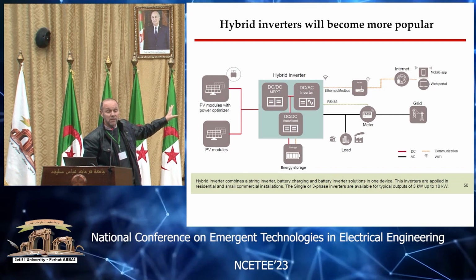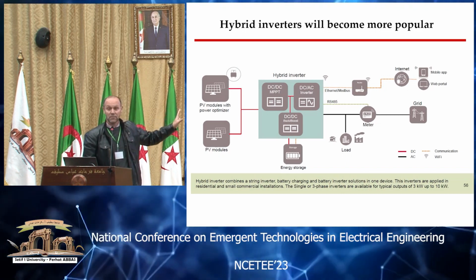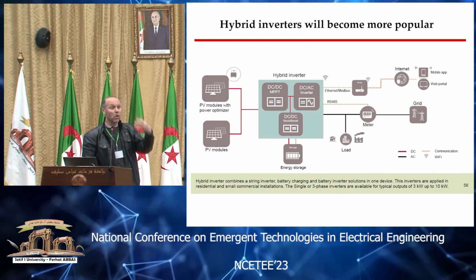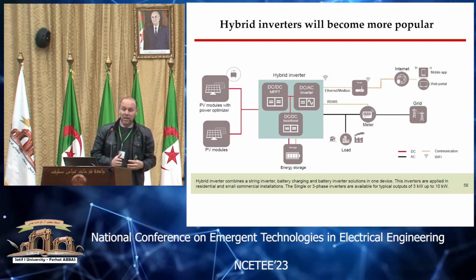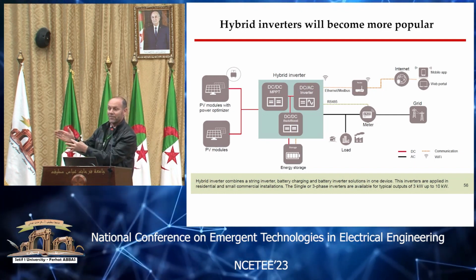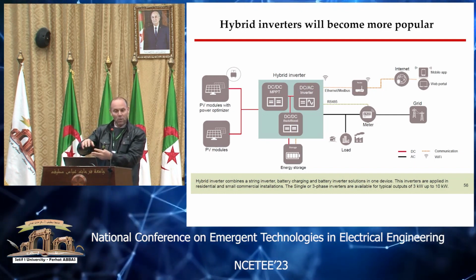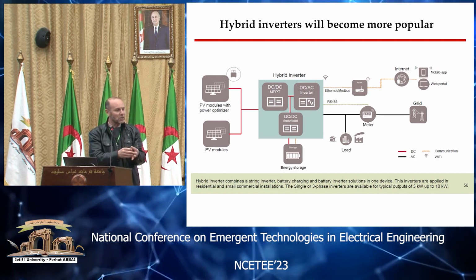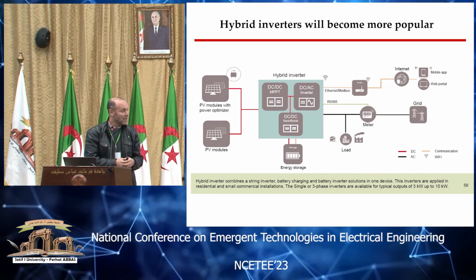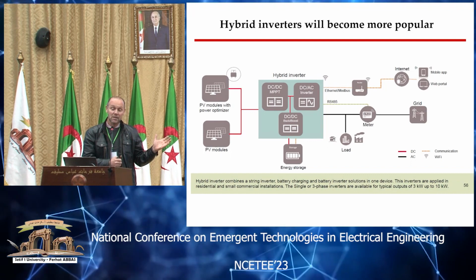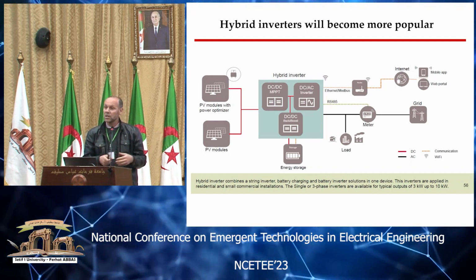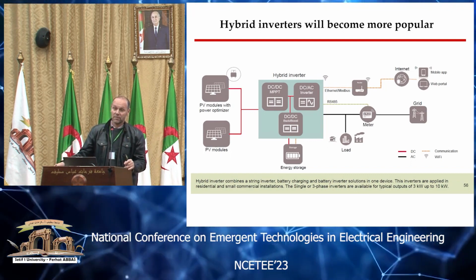Previous inverters are grid-following, meaning they follow the grid. We assume the grid has stable voltage and stable frequency, and we use a phase-locked loop as a reference to inject active and reactive power.